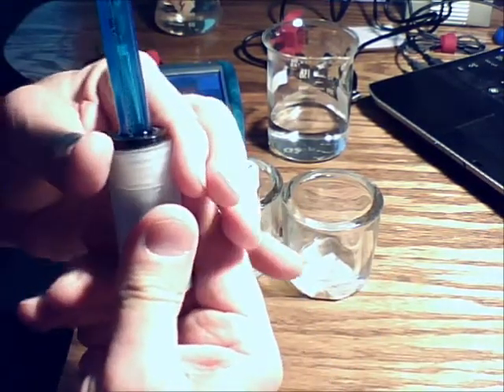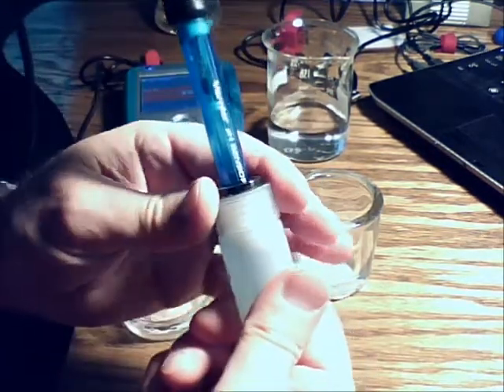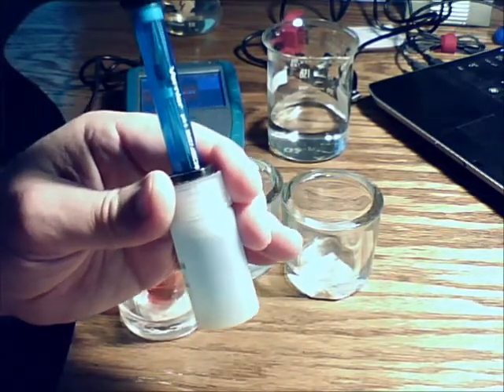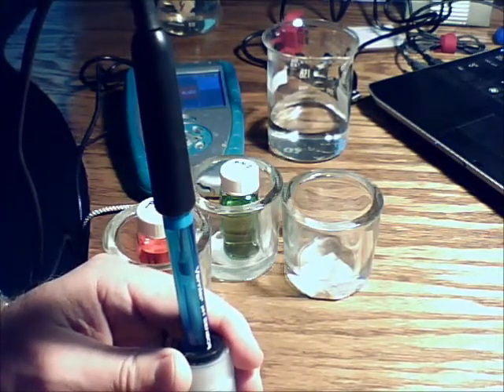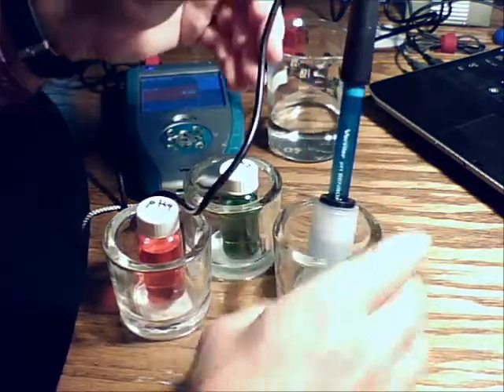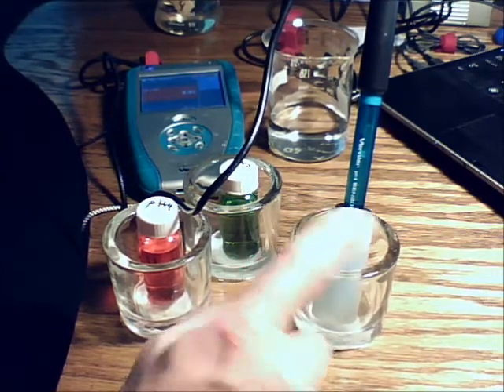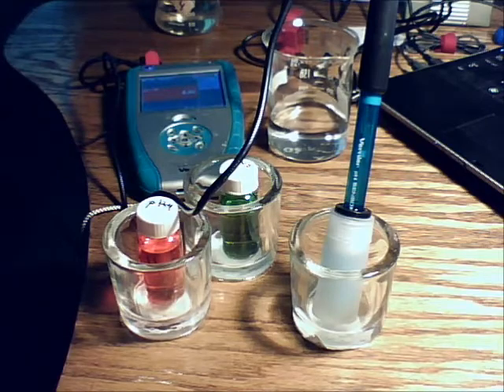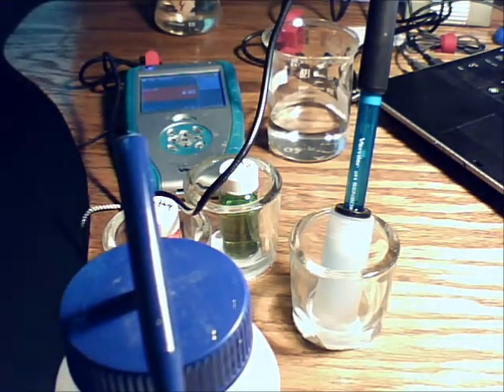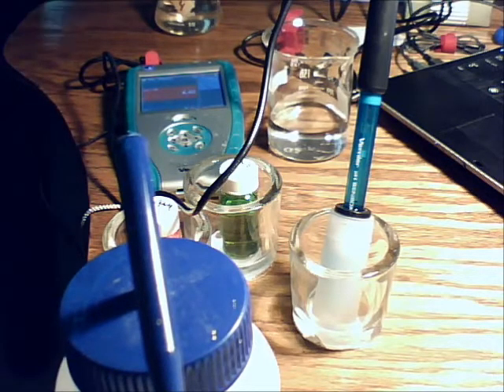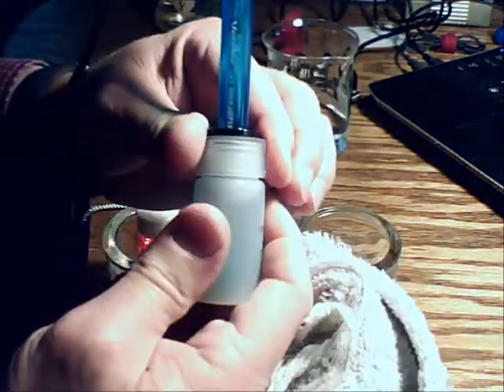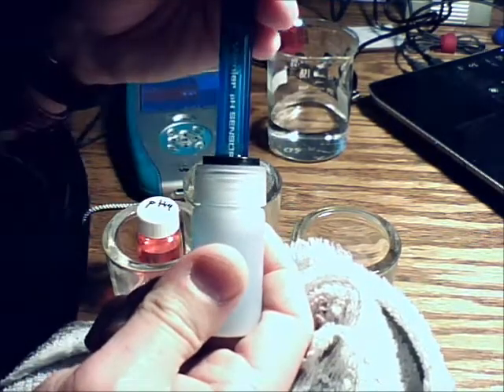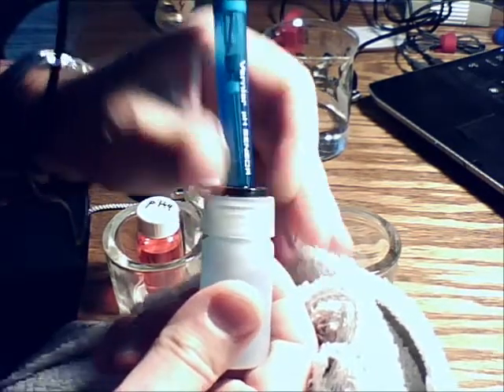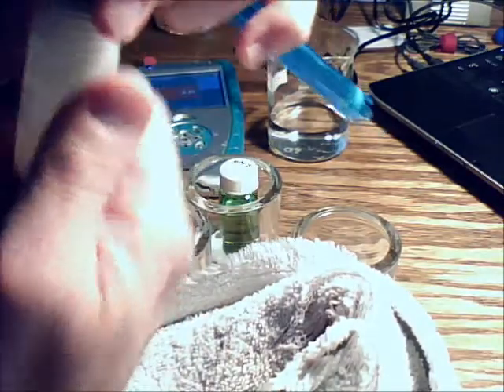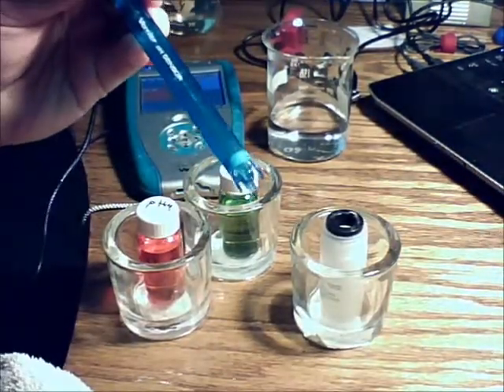And the way this thing is designed is, when this thing is screwed down, it kind of stays in there and seals up. So what I want you to do when you're taking this loose, Philip, would you hand me the water, distilled water on that first lab table? Now I keep it in these, they're candle holders. It keeps them from tipping over because it's really easy to tip these over and make a mess. And what I want you to do is to keep it in those candle holders, keep it from tipping over. To take it out of the solution in which they're stored, you want to just slightly loosen, but not unscrew completely, the cap. And that'll allow some air to flow and allow this to pull out a lot easier. Okay? Like that. Come on out. All right? And then you want to leave this in that holder there so it doesn't tip over.